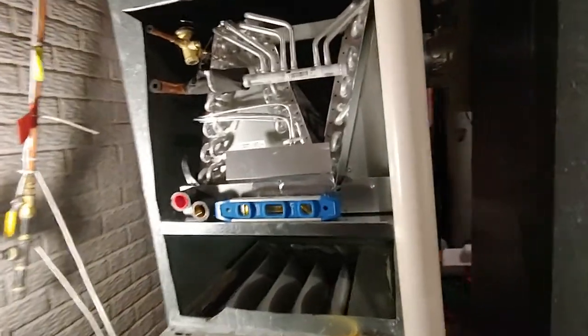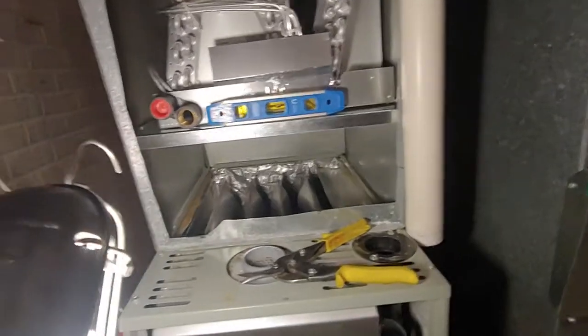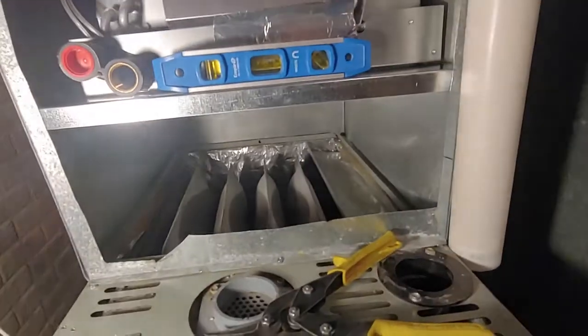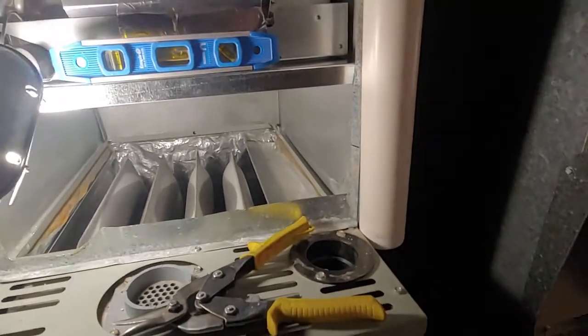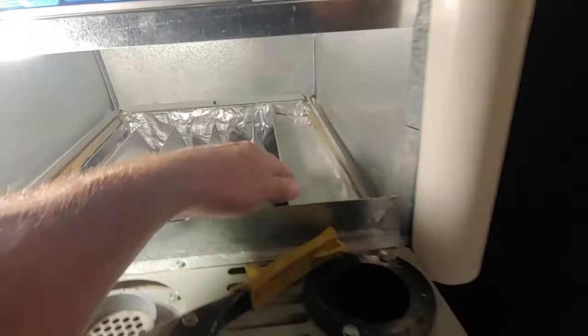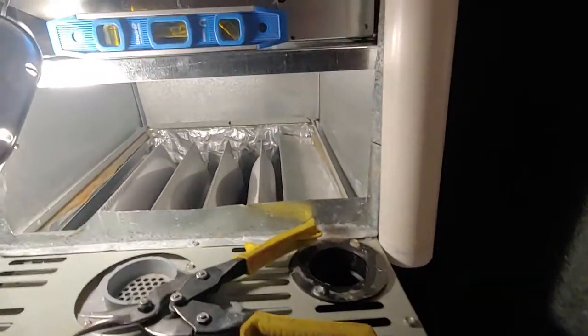This is just a short video on proper A-coil installation. If you're putting one of these on a Trane furnace, you certainly don't want to install it all the way down on the furnace, because the 90-percenters — I think it's just the 90s — have that baffle.